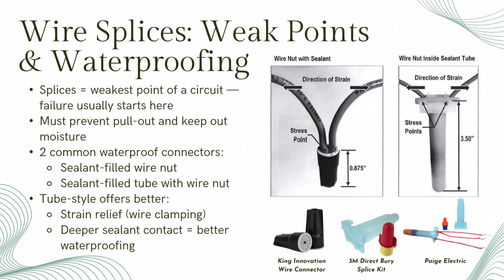Let's be honest, every wire splice is a potential failure point. That's why the quality of your splice really matters. You want a splice that does two things really well. Keeps the wires from pulling apart and keeps water out. The two main connector types are a sealant-filled wire nut and a wire nut inside a sealant-filled tube. The tube version is better. It gives you more contact area with sealant and extra strain relief. The wires are gripped inside the tube, not just twisted together. That makes a huge difference, especially underground.